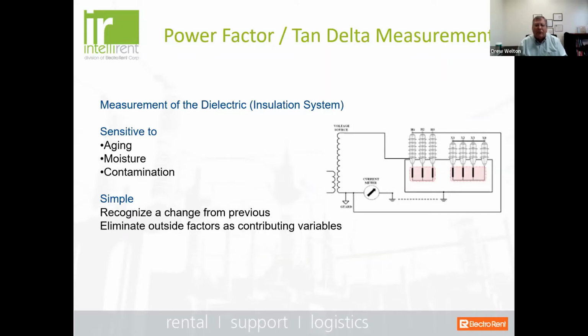So how do we measure the amount of moisture that's in the insulation system itself? Well, we can start with, of course, our power factor or tan delta, or tangent delta, measurements. We know that tan delta measurements are sensitive to aging. They're also sensitive to moisture and contamination. And a power factor test is simple. It can recognize changes from previous measurements, and we can eliminate outside factors as contributing variables. And this is a common test along with your dissolved gas analysis.